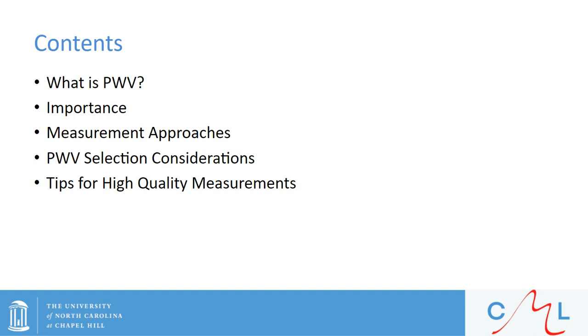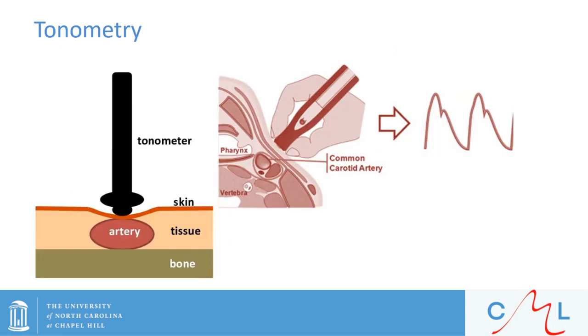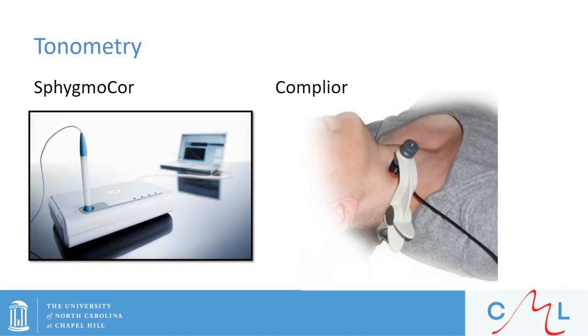We've established that pulse wave velocity is an important measure of arterial stiffness, so now let's discuss some of the measurement approaches. There are several ways to measure pulse wave velocity. These include tonometry, oscillometry, ultrasound, electrocardiogram, photoplethysmography, and transcranial Doppler, among others. Tonometry has been the most widely used method, consisting of applying a force over the center of a superficial artery against an underlying bone. Here are two example devices: on the left, the AtCor SphygmoCor, with the tonometer pen-like device held in a probe holder; and on the right, the complior, with the tonometer held in place by a neck brace.